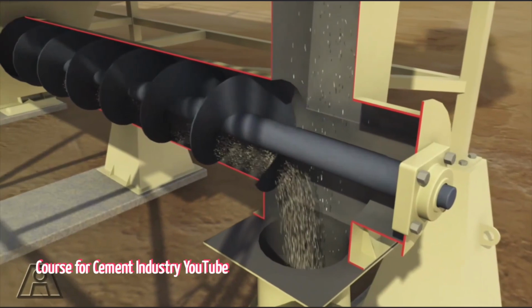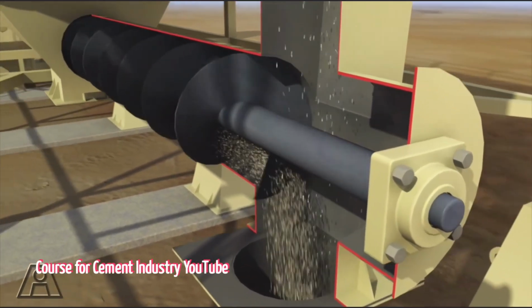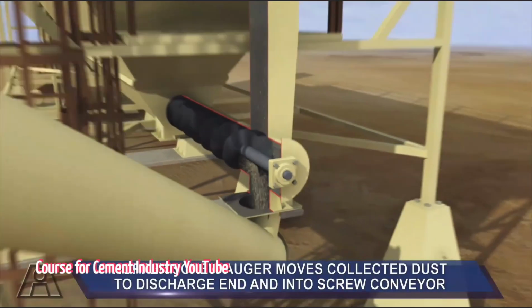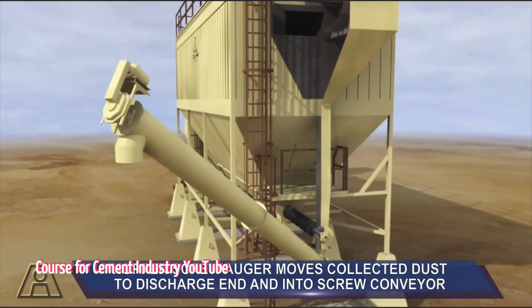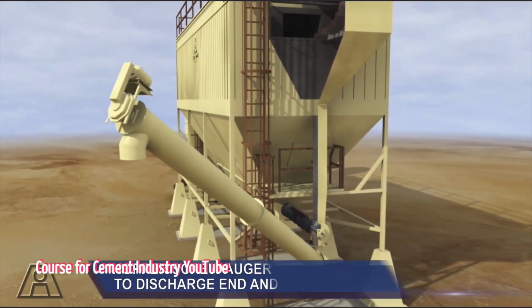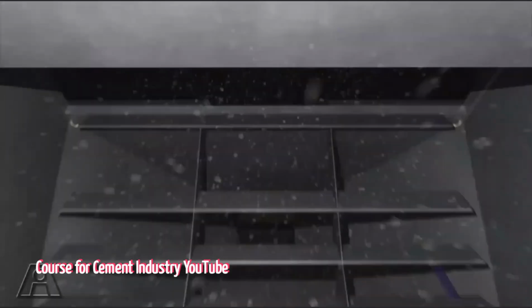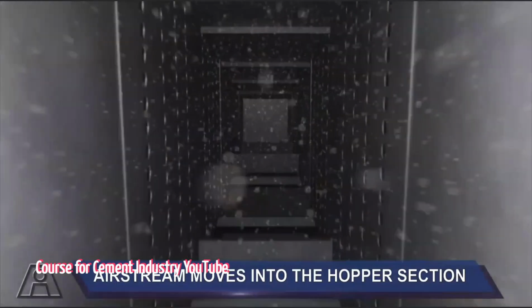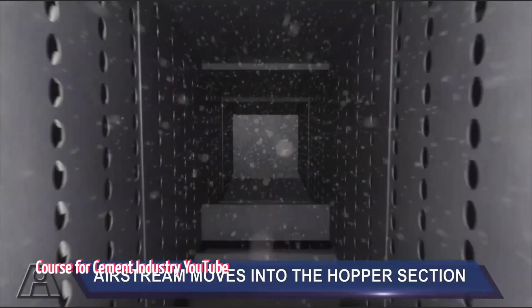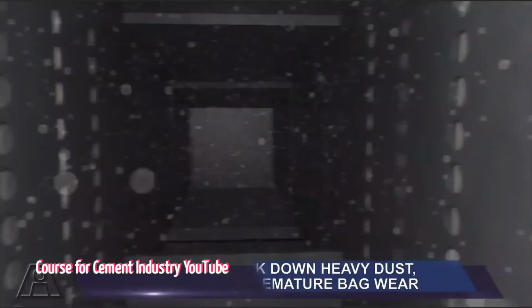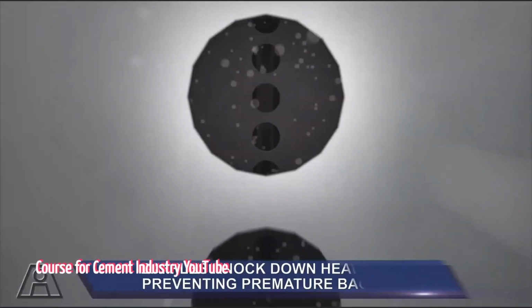Okay, so we have this inevitable buildup, and we have the pressure drop telling us, Houston, we have a problem. You can't just shut down a giant industrial plant every few hours to clean these things manually. So how does the system fix itself? How does it clean the bags automatically? Right, that's where the clever automated cleaning comes in. The most common method by far is the pulse jet cleaning system.